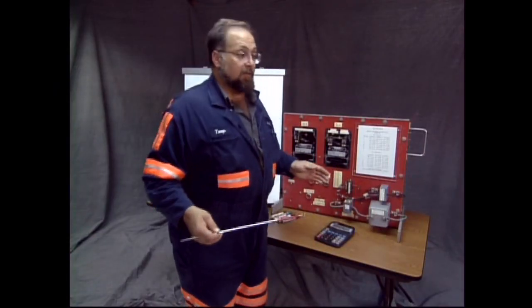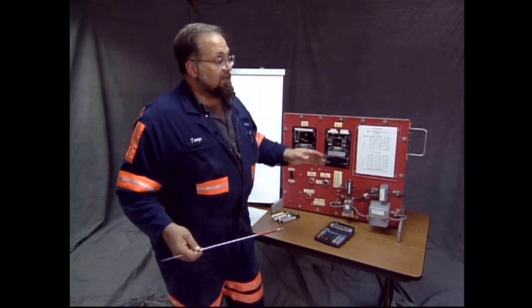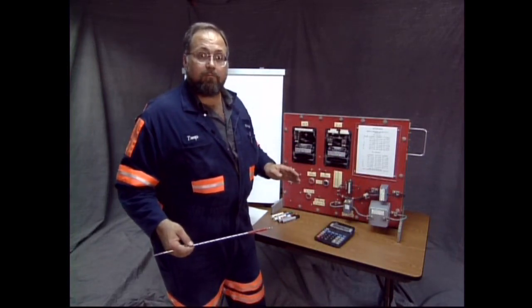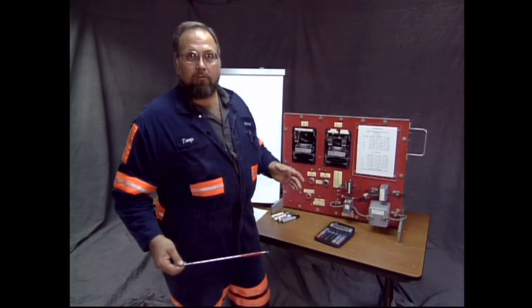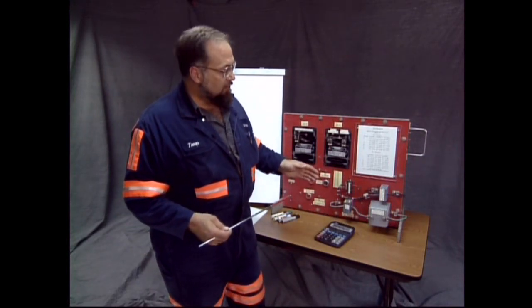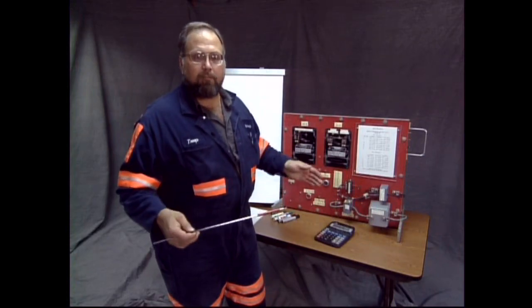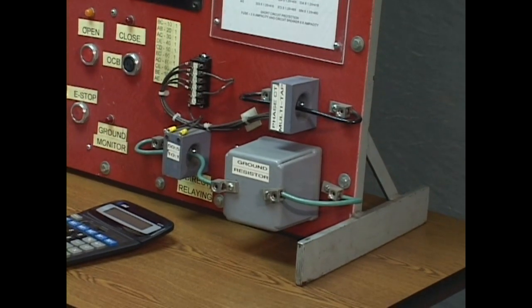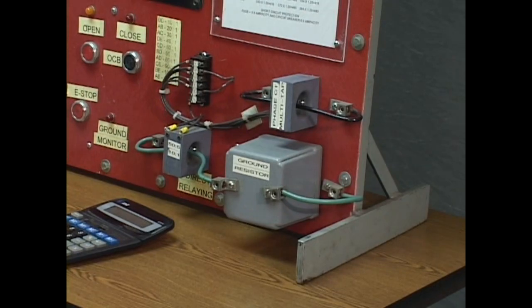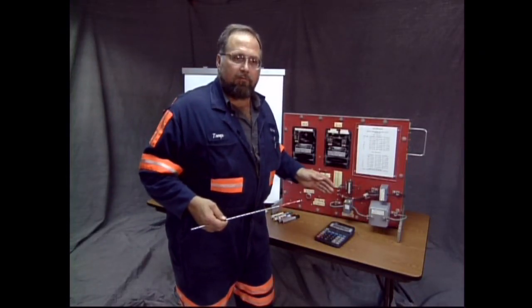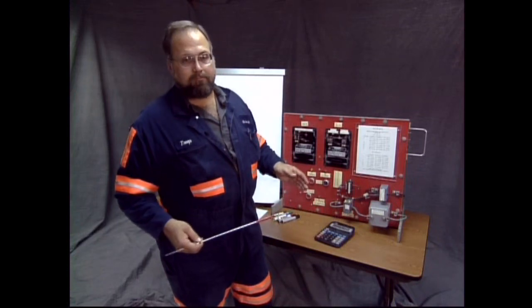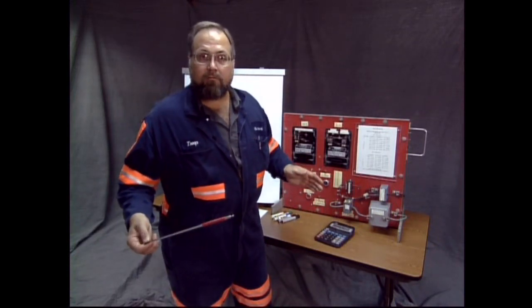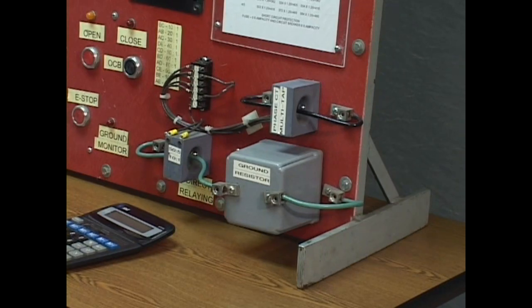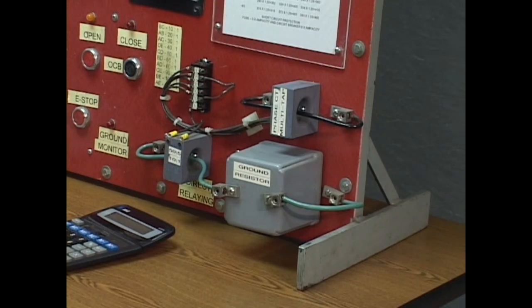Now this has to be tested. You have to read the tag and see how many amps the thing is rated for. And then you have to use Ohm's law, read the ohmic value of the resistor, multiply that by the current, and that will tell you how many volts this resistor will drop. That figure needs to come within 100 volts of the value of any phase. So that if you have a ground fault, the ground resistor will deal with it and limit it to 25 amps and no more than 100 volts external to the resistor. I'm going to show you how to figure that later.